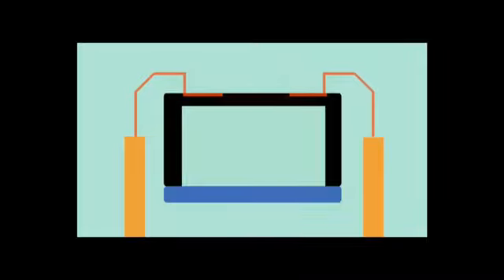The piezo-resistive measuring principle exploits the change in the sensor element's electrical properties when it deforms. The force exerted on the sensor element as pressure is applied causes it to deform, and in doing so changes its electrical properties. The electrical signals, which change together with the pressure, are transmitted outward through ultra-thin bonding wires. This allows the change in the electrical signals to be measured.